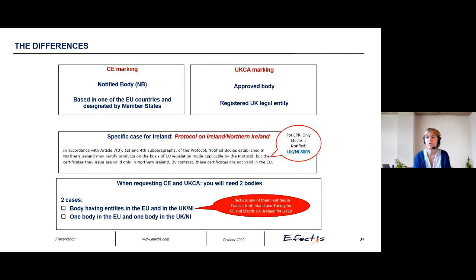Now the differences, because of course it would be too good if everything was the same. For CE marking we have what we call notified bodies, usually seen as NBs. For UKCA marking you will have something called approved bodies. Where we are lucky is that the numbers of previous UK notified bodies have been kept when they were designated as approved bodies, and if you already had DOPs or CE logos with their number, you can keep it even if you change CE for UKCA.